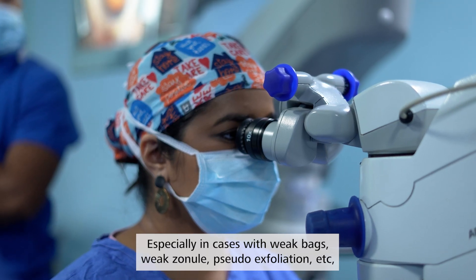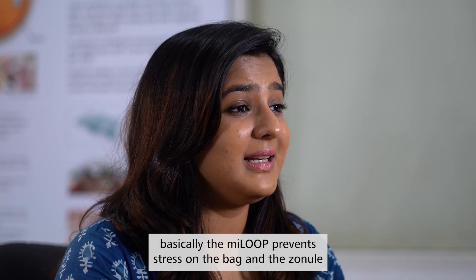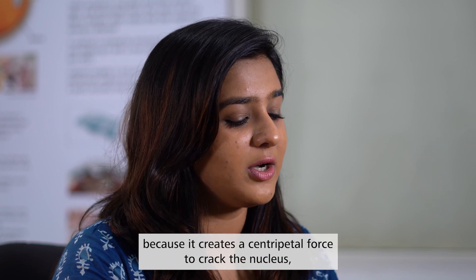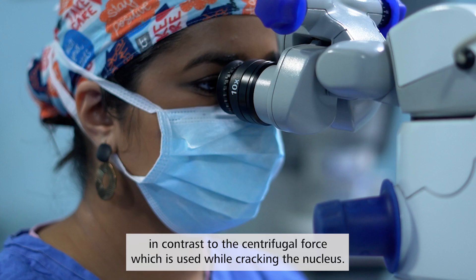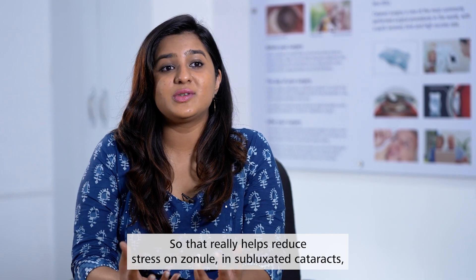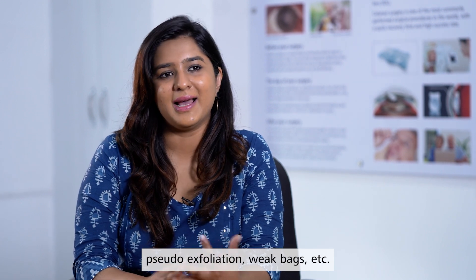Especially in cases with weak bags, weak zonules, pseudo-exfoliation, etc. — the miLOOP prevents stress on the bag and the zonules because it creates a centripetal force to crack the nucleus, in contrast to the centrifugal force used while cracking the nucleus conventionally. That really helps reduce stress on zonules in subluxated cataracts, pseudo-exfoliation, and weak bags.